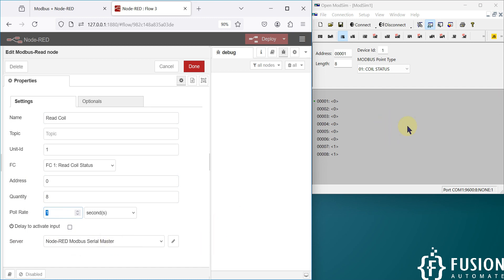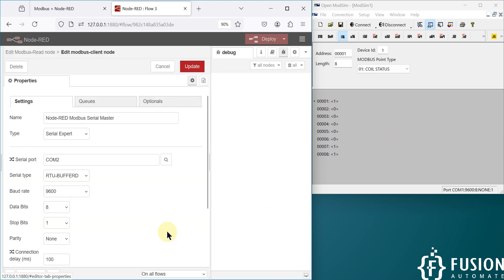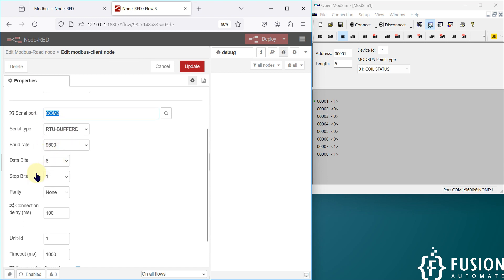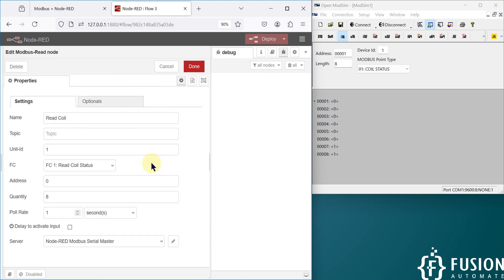The server is Node-RED Modbus serial master, as we are going to connect with a Modbus serial device. If you click on the pencil icon, here are the connection details: we are connecting on COM2, serial type is RTU, baud rate 9600, data bits eight, stop bit one, and parity none. Here is the serial expert and we have provided the name. That's all you have to configure.